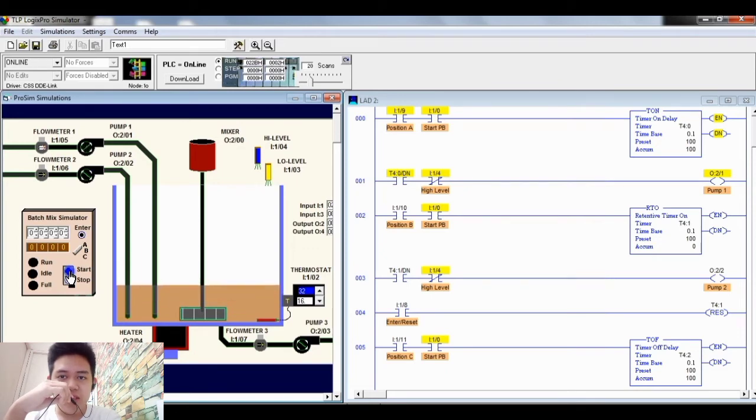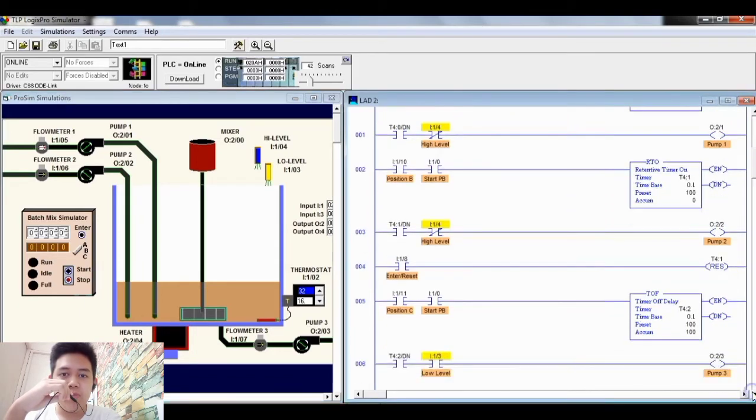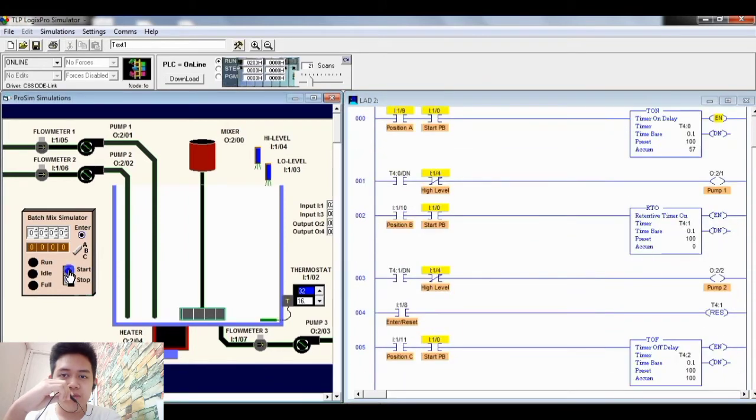Once the done of the timer on delay becomes true, the examine if closed T4:0/dn becomes true because they have the same address. Once the examine if closed T4:0/dn becomes true, the pump 1 OTE starts because rung 001 becomes true.